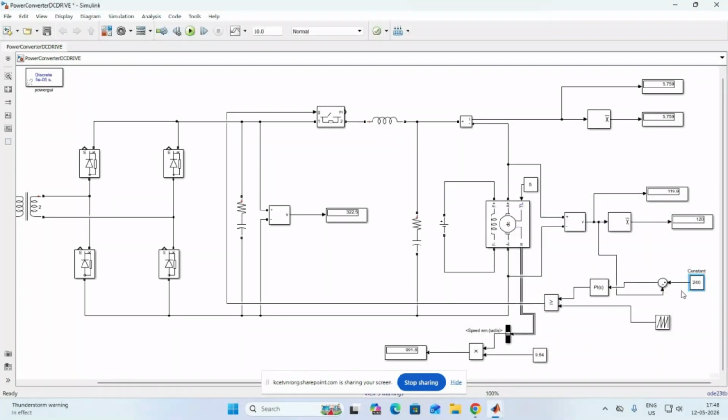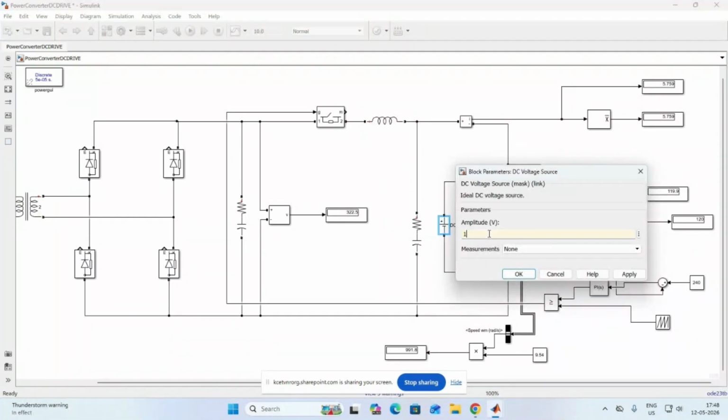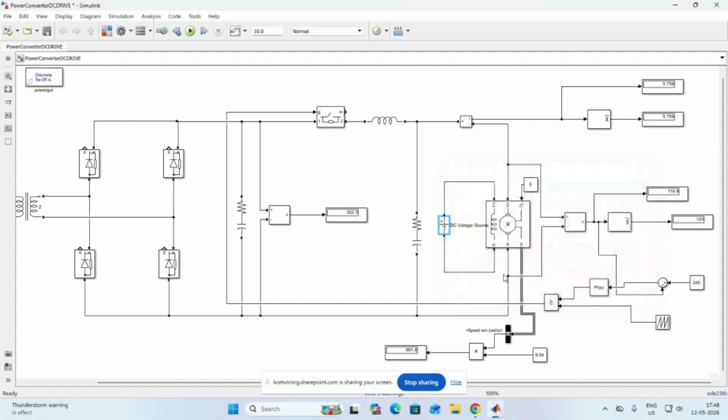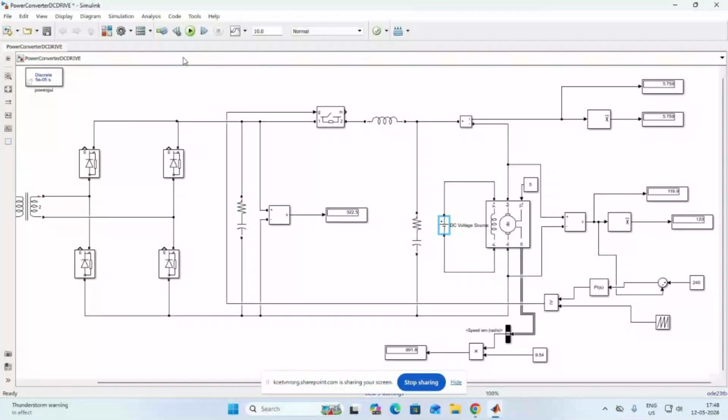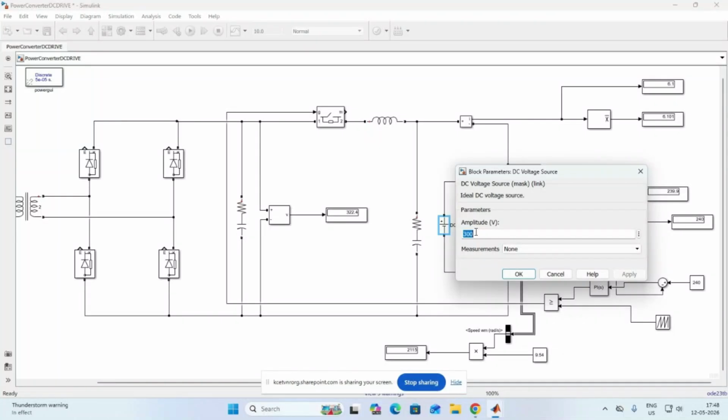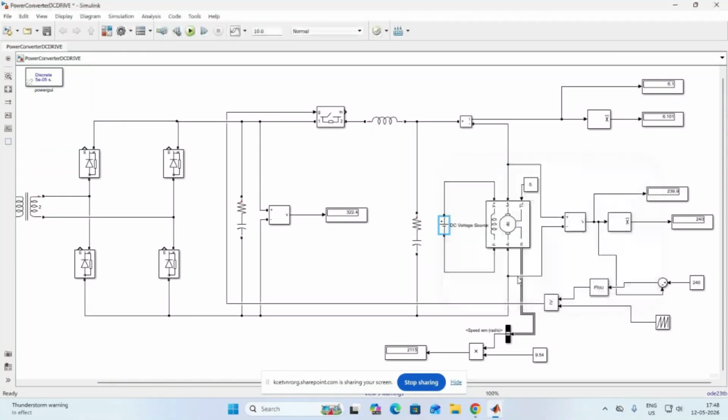So now I am increasing armature voltage from 120 to 240, the normal value. Now I am reducing field from 300 to 150. I have reduced nearly 50 percent of the voltage. That is called field weakening. So if you are reducing the voltage, your field also gets reduced to 150. Now see, first we will check for 240 and 300 for the 5 HP motor. It's 2155. Now I am reducing field to 150.